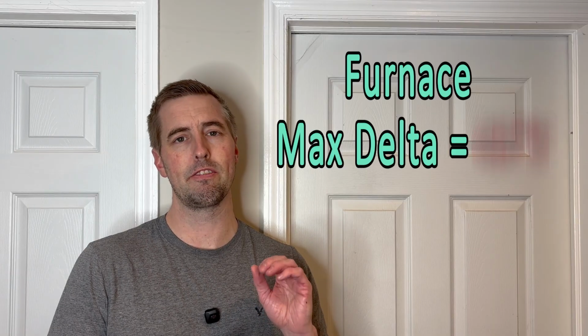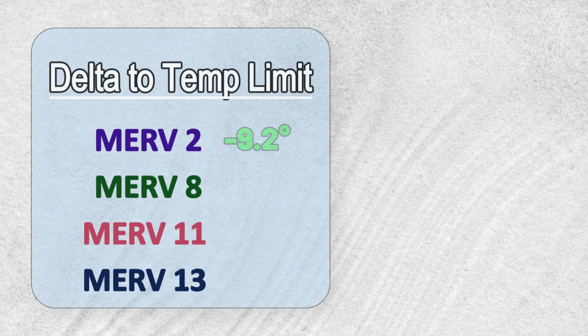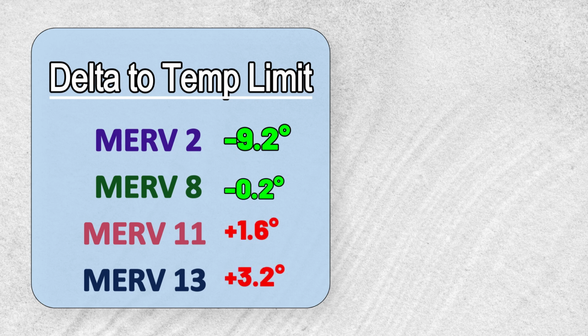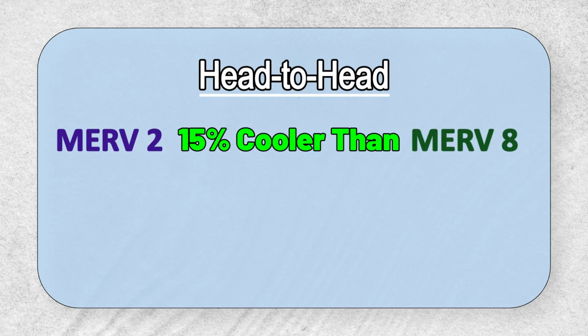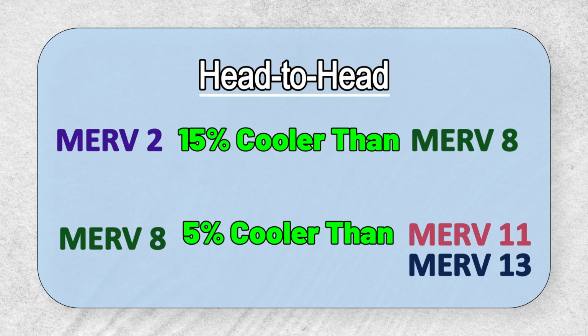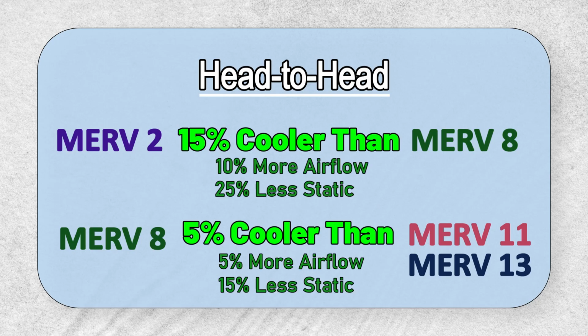And as mentioned earlier, our furnace has a temperature limit of 65 degrees Fahrenheit, meaning if the difference between the supply and the return exceeds 65 degrees, the burners are going to shut off, fan's going to continue to run, it's going to be inefficient essentially. And what we saw here is our MERV 2 remained around 10 degrees lower than that 65 degree limit. So plenty of bandwidth to hopefully not hit that limit. Whereas the pleated filters, we saw those deltas hover right around the 65 degree mark. And with our comparisons, we saw the MERV 2 resulted in a delta of about 15% cooler than the MERV 8, and our MERV 8 was about 5% cooler than the MERV 11 and 13. And we can see how the lower deltas correlated with the higher airflows and the lower statics.